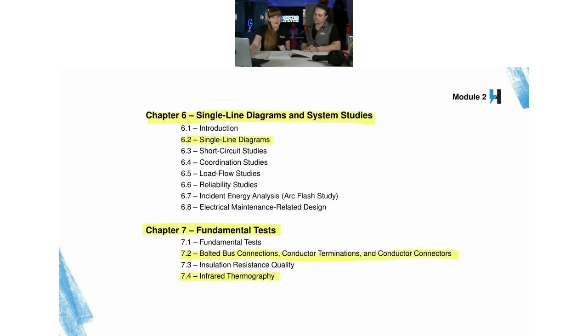Mm-hmm. All right. And then chapter 7, fundamental tests. So it goes over the different basic things that every piece of electrical equipment should be tested for, whether it be making sure that you have the right tightness for torque verification, or contact resistance testing, making sure that there's not too much resistance, insulation resistance quality, as well as infrared thermography. There's a whole section about that, making sure that you are inspecting each of the sections of electrical equipment that have a tendency to cause the most issues in a facility. Mm-hmm. Moving right along to chapter 8.